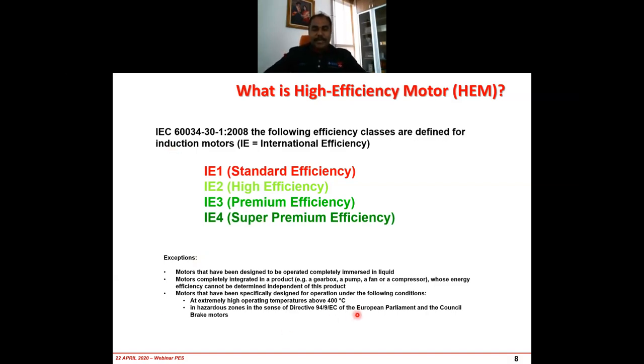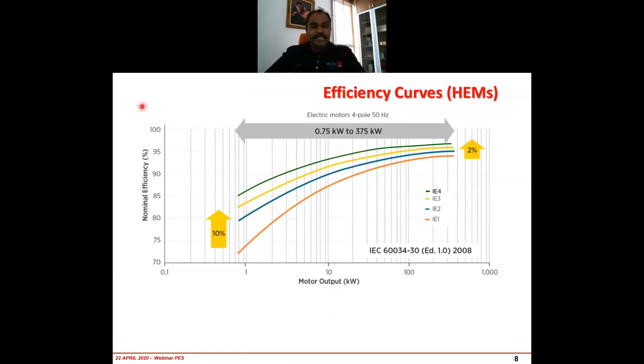Now, next. Again, in the graph format, this is the efficiency, and this is the power, efficiency versus power, the rated power of the motor. If you notice, the first one is IE1, then the second one, IE2, IE3, and IE4. As you can see, IE4 gives you bigger savings, I mean higher efficiency, compared to 3, 2, and 1. For the smaller size motor, the difference can be about 10% in the efficiency, and for the bigger size, the difference can be about 2%, which is 2% of a large amount, a big amount of kilowatts.